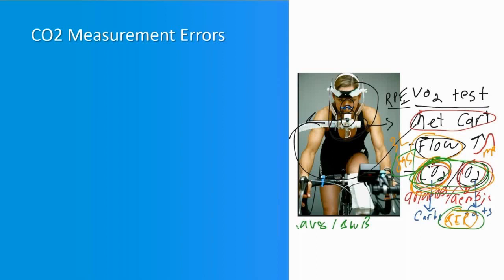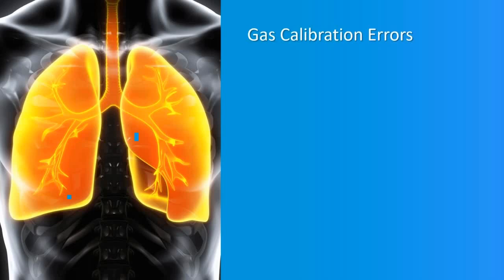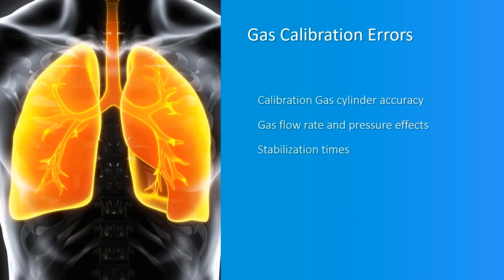The carbon dioxide analyzer accuracy is a significant source of VCO2 error, and like the oxygen analyzer, the CO2 analyzer is also subject to interferent gas errors. Calibration gas cylinder accuracy is an important issue; it is best to use a primary laboratory standard accurate to 0.02% absolute. All gas analyzers are sensitive to changes in the pressure of the gas — this must be either controlled or minimized by calibrating under the same conditions as sampling. Insufficient gas analyzer stabilization times during calibration produce erroneous readings; you need to wait for the gas analyzers to stabilize completely.